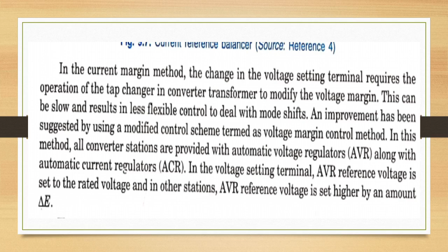An improvement has been suggested by using a modified control scheme termed the voltage margin control method. In this method, all converter stations will be provided with automatic voltage regulators (AVR) along with automatic current regulators (ACR). In the voltage setting terminal, the AVR reference voltage is set to the rated voltage, and in other stations, the AVR reference voltage is set higher by an amount delta E.